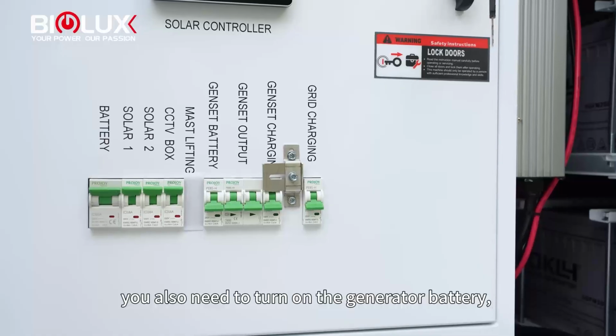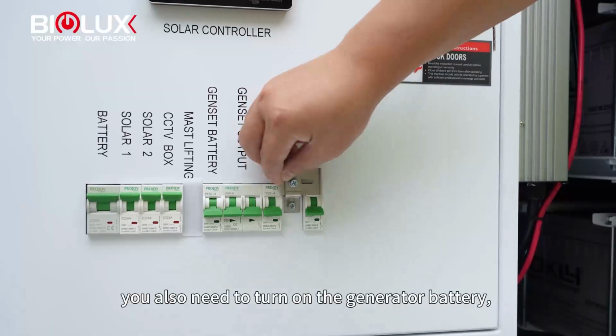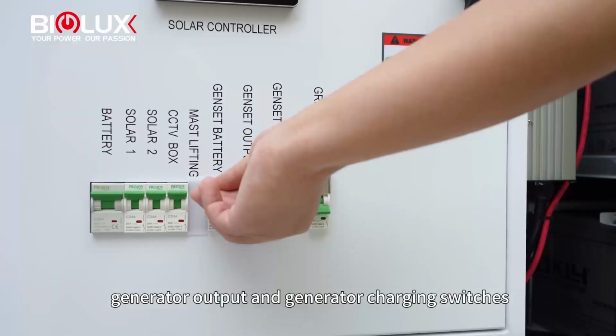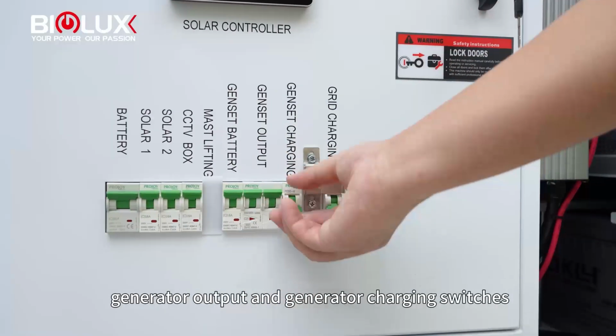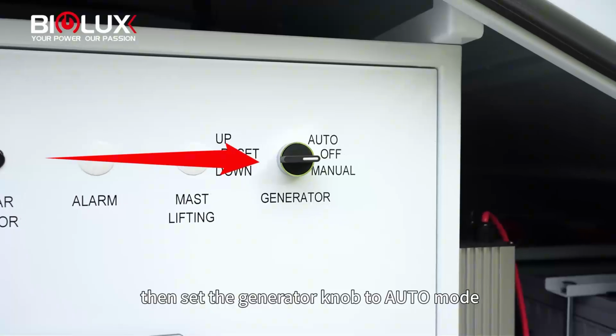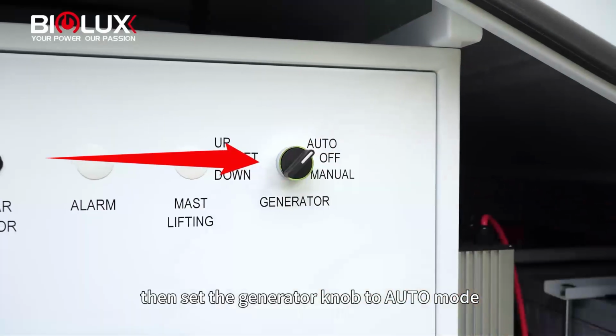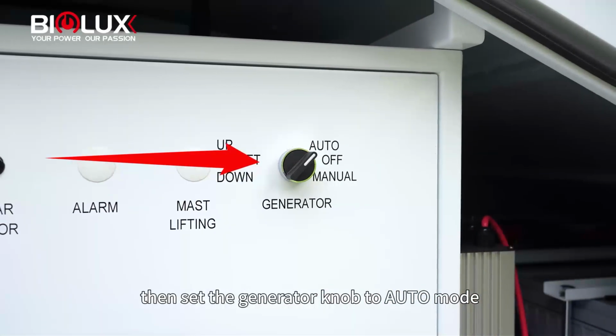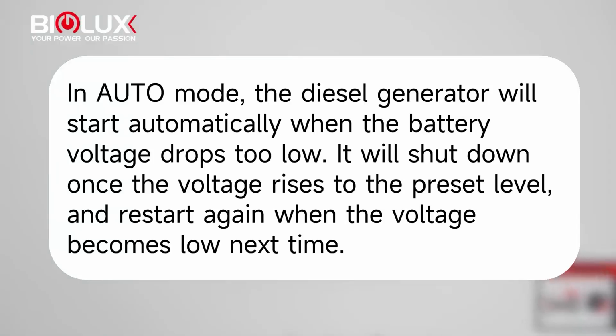For units equipped with a generator, in addition to the above steps, you also need to turn on the generator battery, generator output and generator charging switches. Then set the generator knob to auto mode. In auto mode, the diesel generator will start automatically when the battery voltage drops too low. It will shut down once the voltage rises to the preset level, and restart again when the voltage becomes low next time.